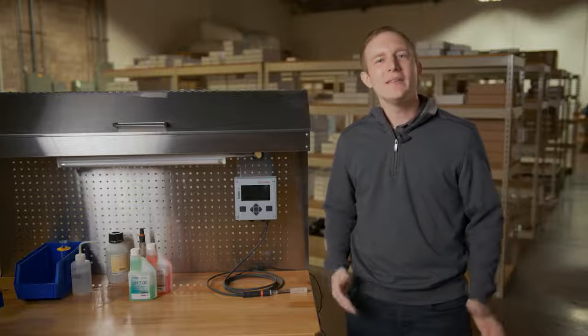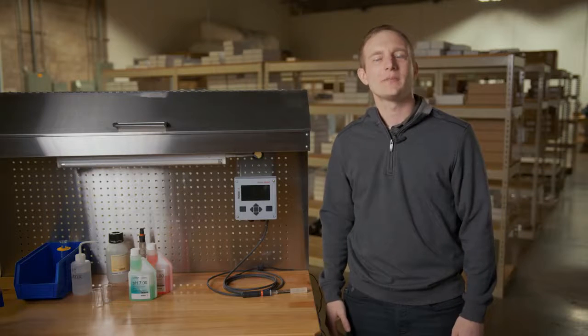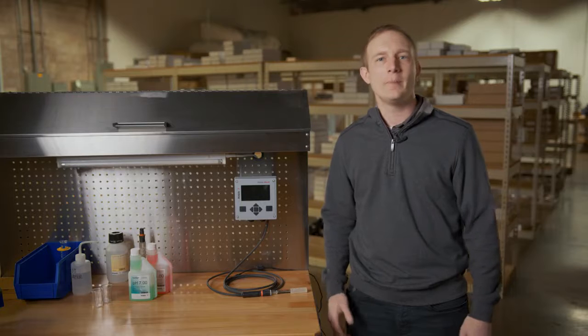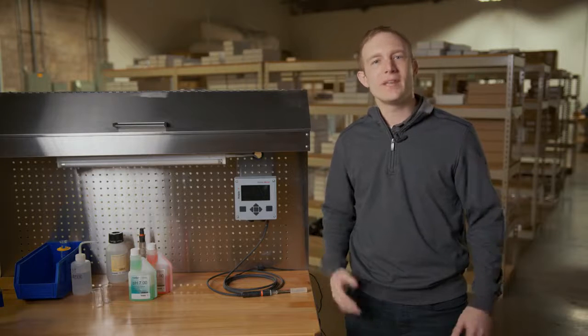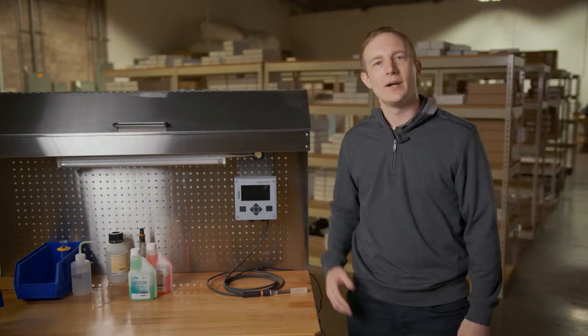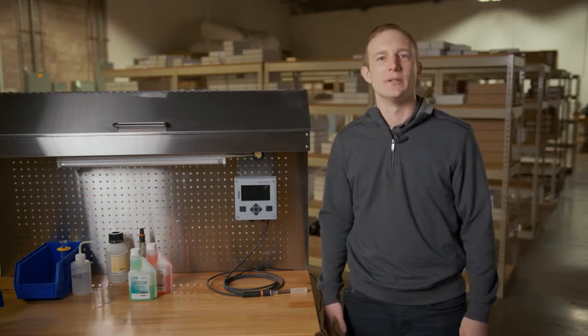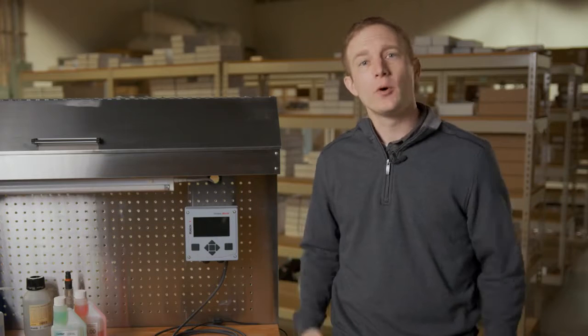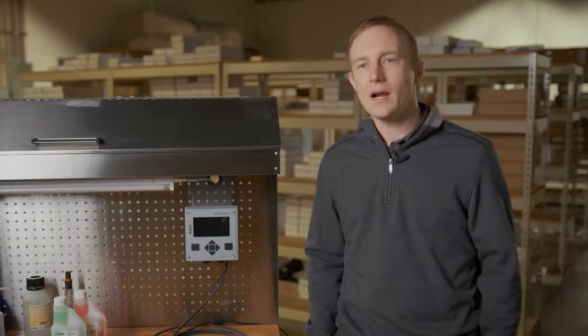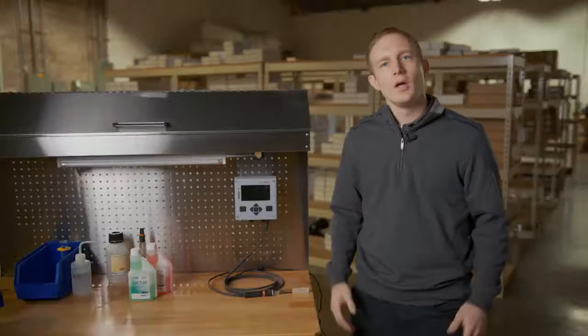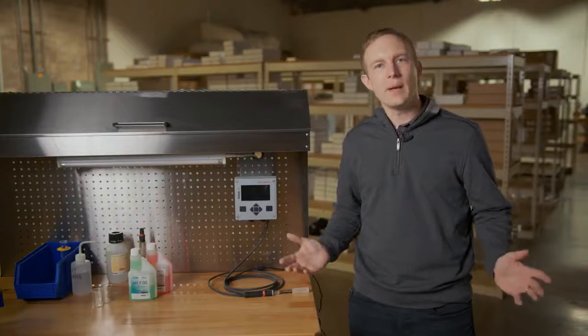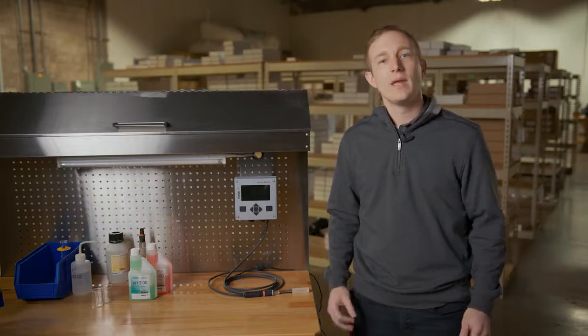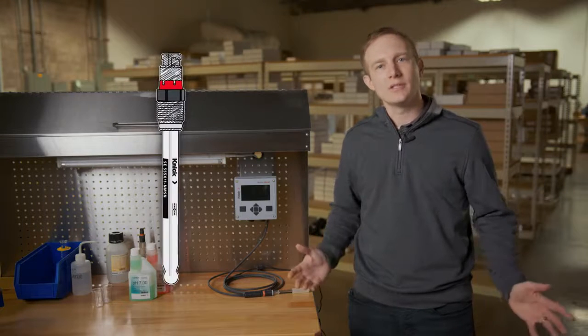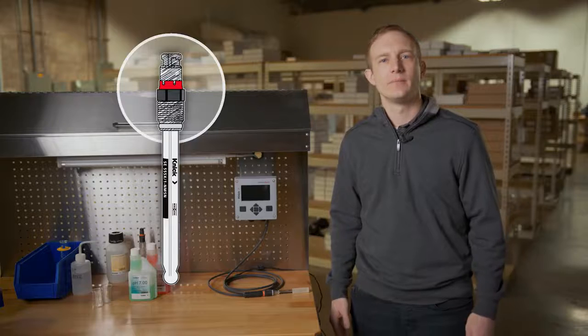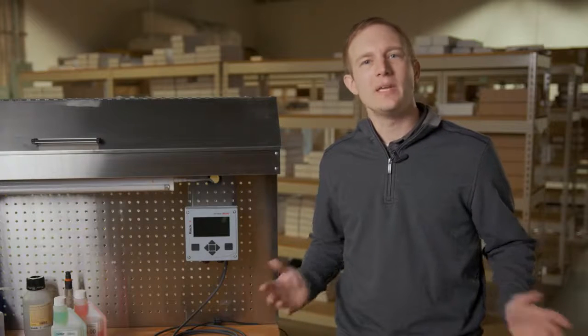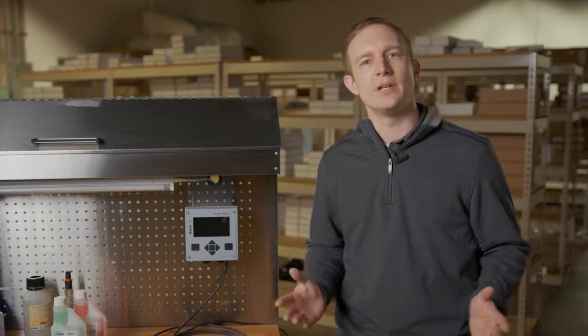Hello everyone. In this video, we will walk you through the steps to perform an automatic 2-point pH calibration using the Knick Stratos multi-transmitter and a Memosens pH sensor. The calibration will be performed offline in a controlled environment right here in our workshop. Our connected pH sensor is a Memosens smart digital sensor. The calibration will be written and stored in the head of the sensor. These steps, however, can also be utilized when performing a calibration in the field.